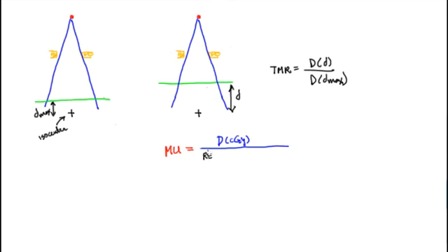It's divided by a reference value. That reference value is the number of centigray per MU under reference conditions, and it's typically 1, times SC, collimator scatter factor, SP, phantom scatter factor, and the TMR, which depends on the depth and the field size. I'll explain what these SC, SP factors are in a minute, but let's just take a simple example.